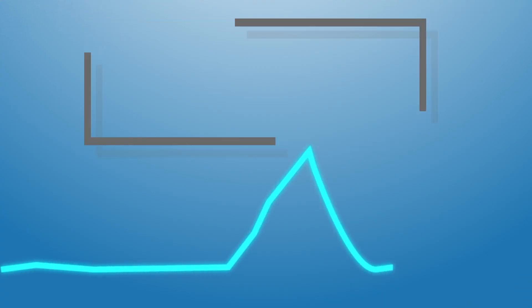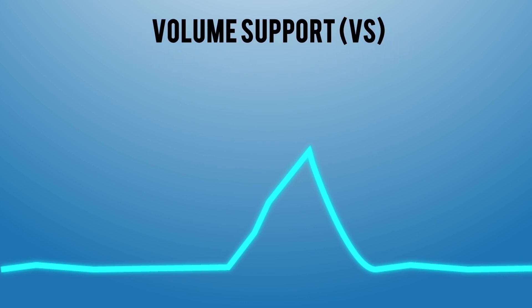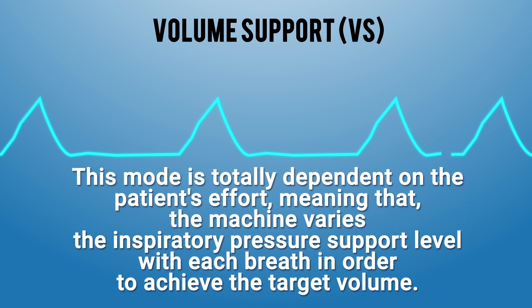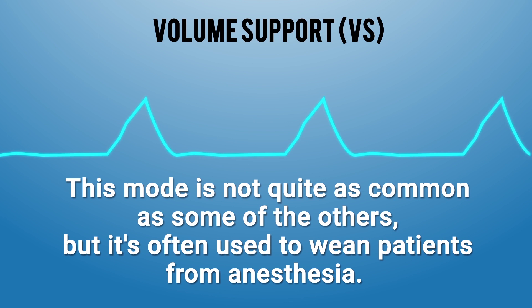The last spontaneous mode is Volume Support (VS). This is a mode in which the ventilator delivers a supported breath to help the patient reach a set tidal volume. It is totally dependent on the patient's effort, meaning the machine varies the inspiratory pressure support level with each breath to achieve the target volume. This mode is not as common as others but is often used to wean patients from anesthesia.